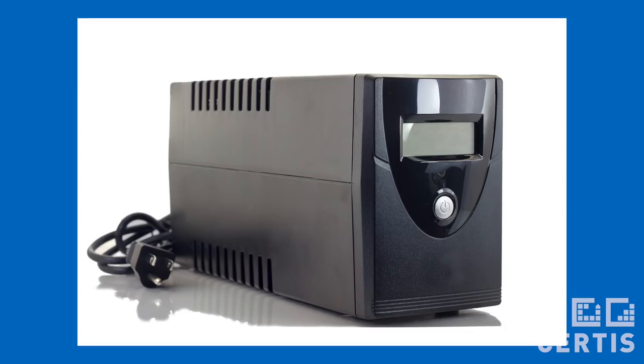At Certis, we decided that if the UPS simply plugs into the wall, then it's an appliance, no different from the servers themselves or the microwave oven in the kitchen, and therefore the requirements would not apply. However, if the battery were to be hardwired, then it would be considered as part of the building, which would then trigger the need for fire separation or a performance solution.